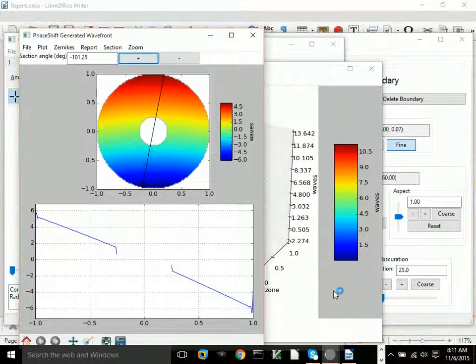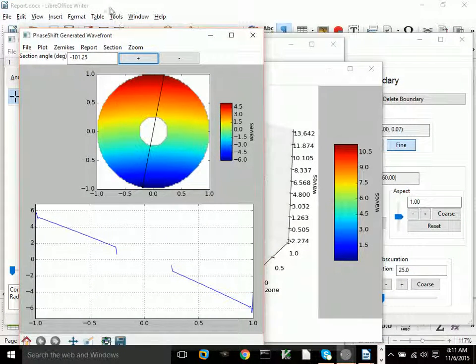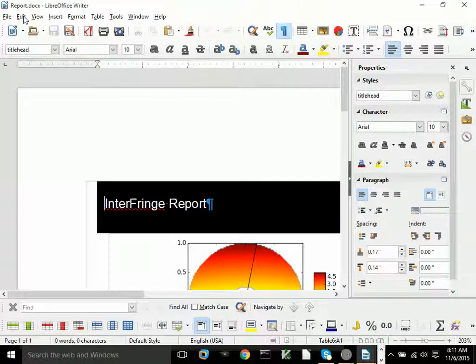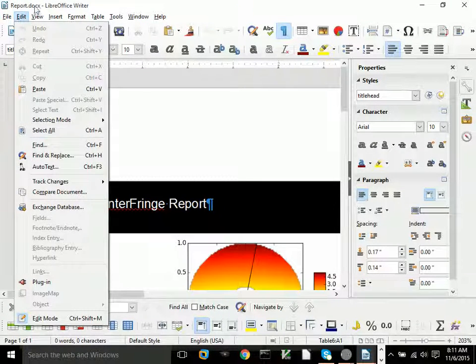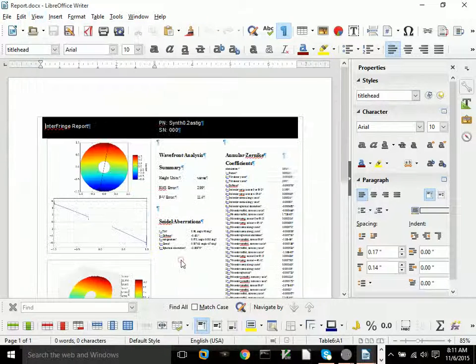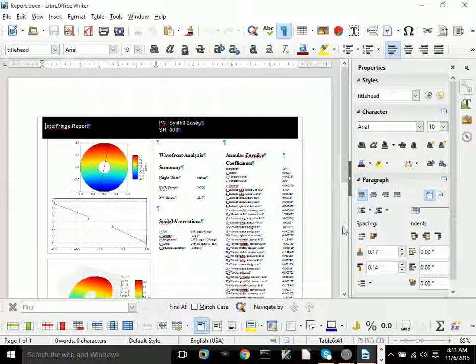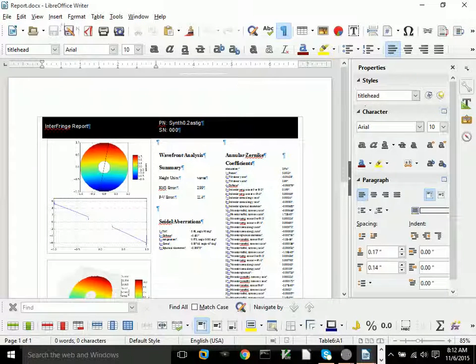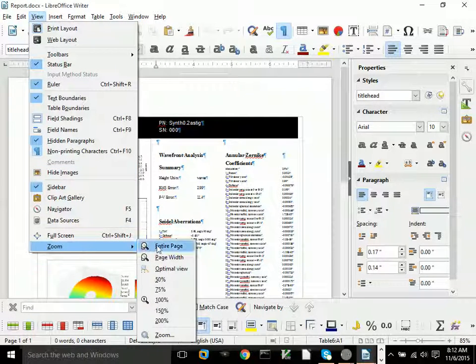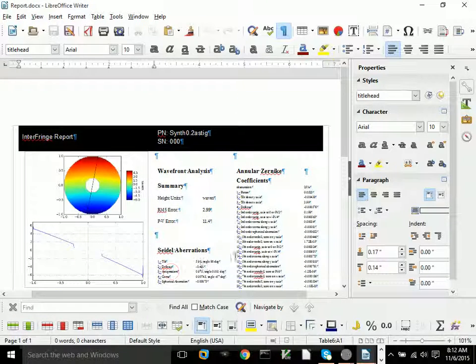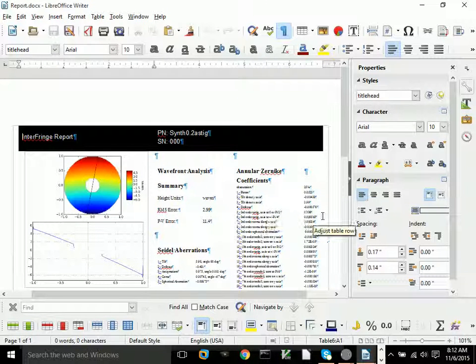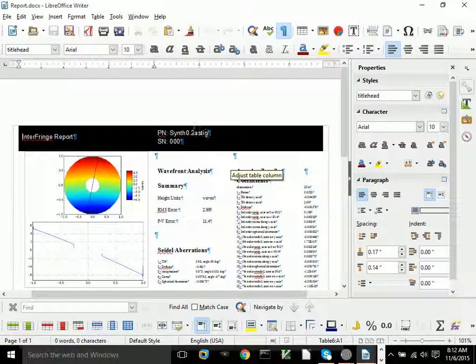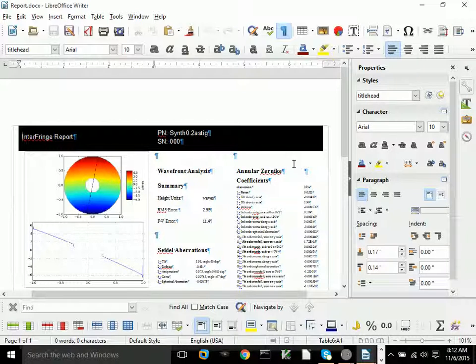And the result is a report similar to the previous one. This one hopefully will show the amount of aberrations that we've got. As you can see, I have to zoom in a little bit so you can see the amount of astigmatism is 0.199. It was originally specified at 0.2, so it's an accurate, nice-looking result.